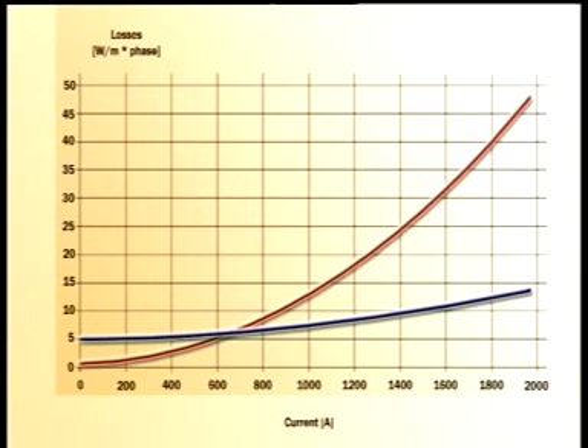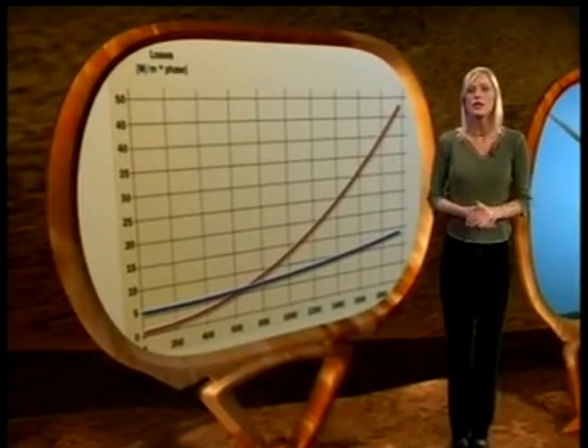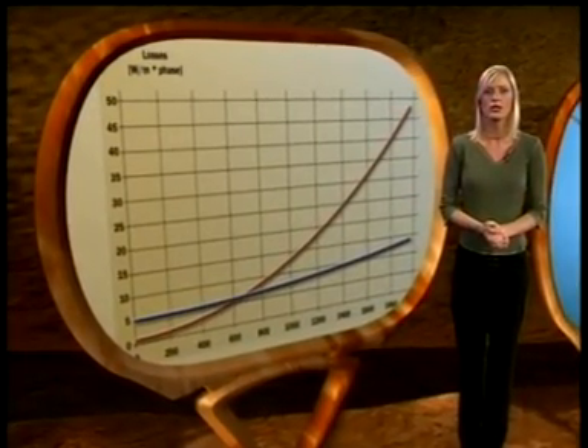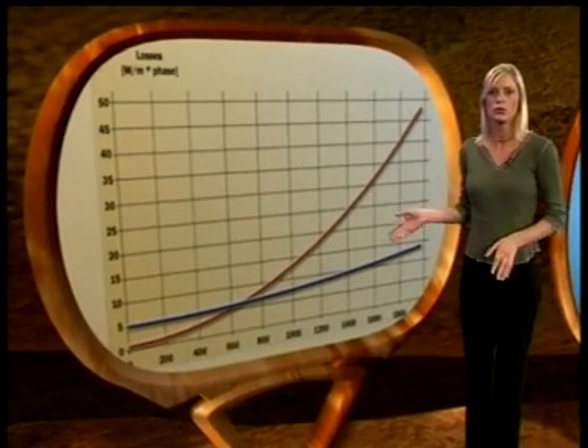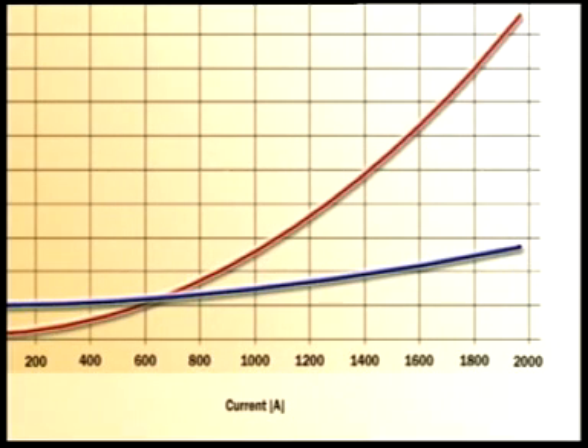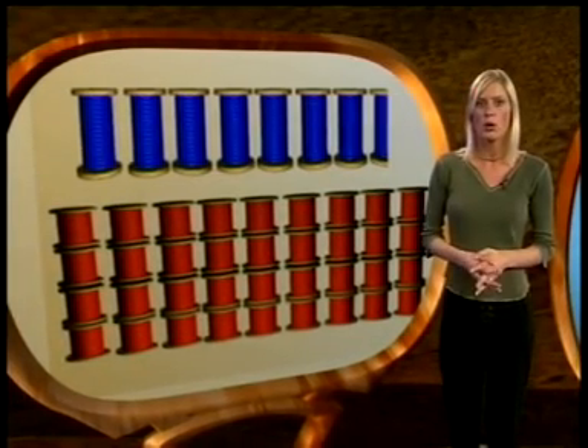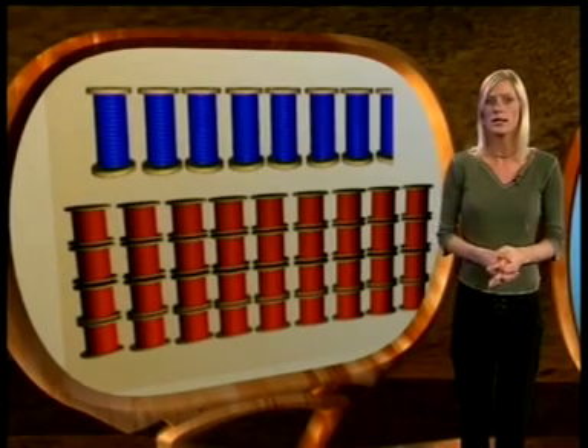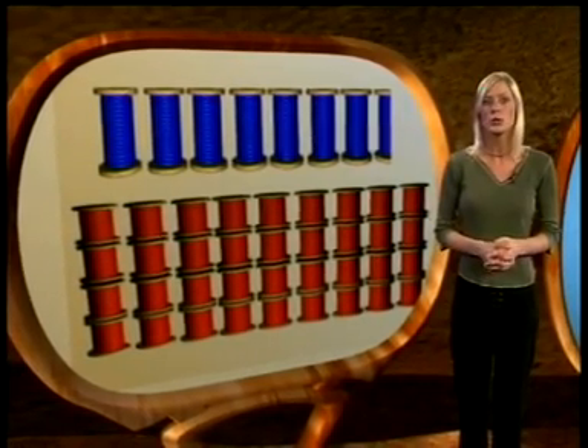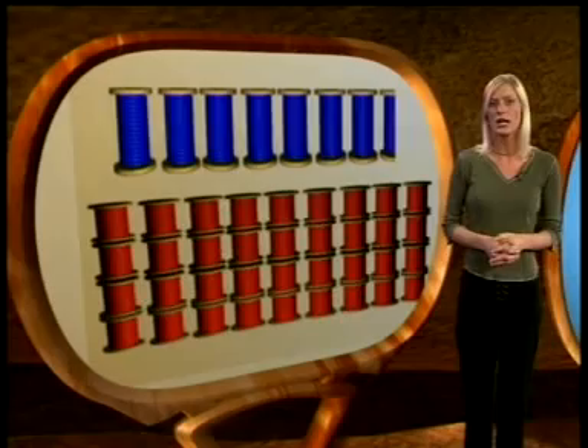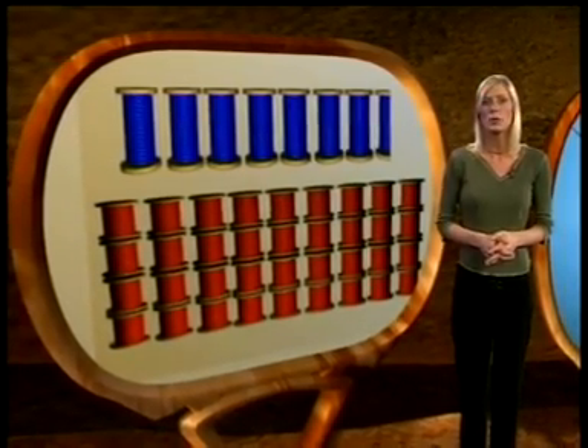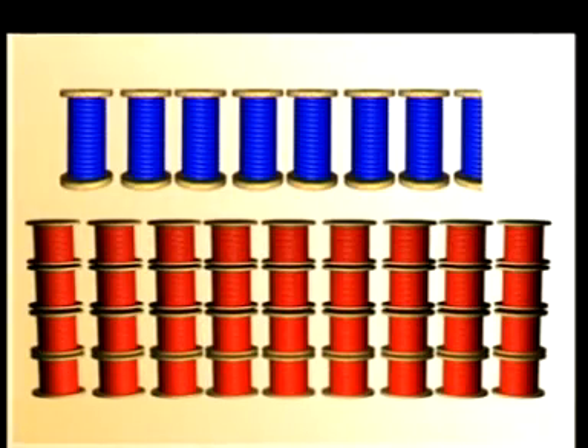Superconducting cables can offer the advantage of lower loss, lighter weight, and a more compact dimension. A set of two conventional cable systems that carry 200 megawatts will have losses described by this red curve. These two cables can be replaced by a single HTS cable with a lower loss at higher loads. The high performance of the superconducting materials means less material is required. For example, a 5-kilometer long power line would require approximately 36 cable drums of copper cable, each weighing 20 to 30,000 kilos. Because the HTS cable is lighter and more compact, it can be put onto only 7 to 8 drums of the same weight.